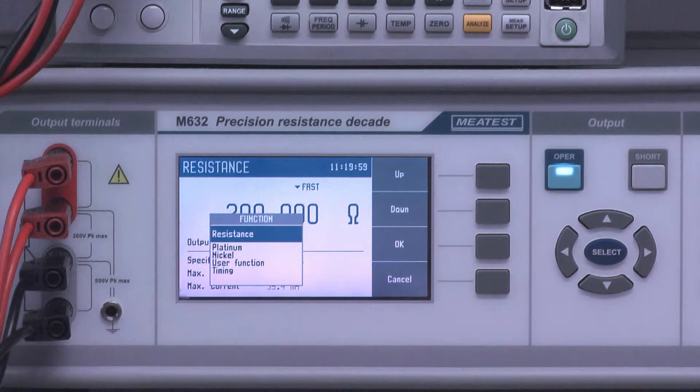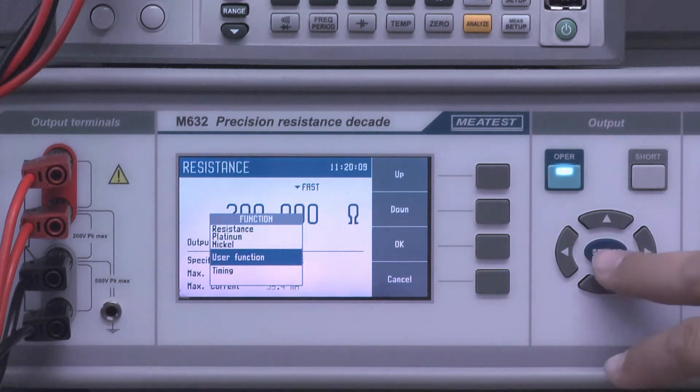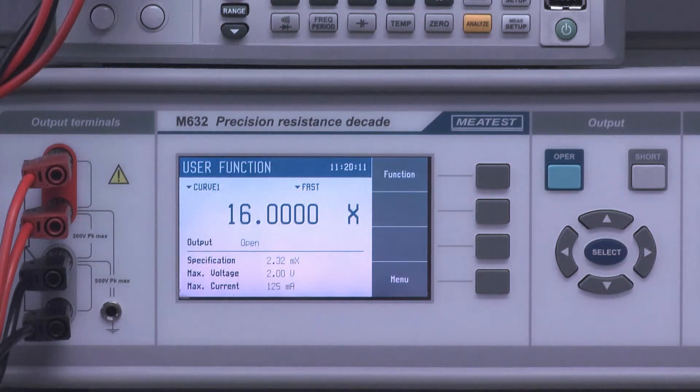As you can see, the M632 can be a resistance standard, an RTD simulator of platinum and nickel sensors, or you can set it up using your own functions, which can be really useful for calibration of specific resistance-based sensors.